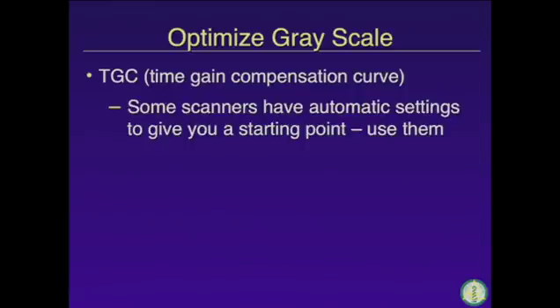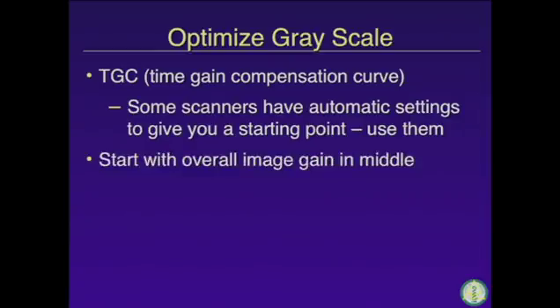So the other thing we need to do is to optimize the TGC, and that's the time gain compensation curve. Some scanners have an automatic setting to give you a starting point. When I started doing this, when they came out, I thought, oh, I don't want to use that. I can get the pictures perfect without them. And it's true, I can, but it's going to take me longer. So use them just as a starting point and then alter it as you wish thereafter.